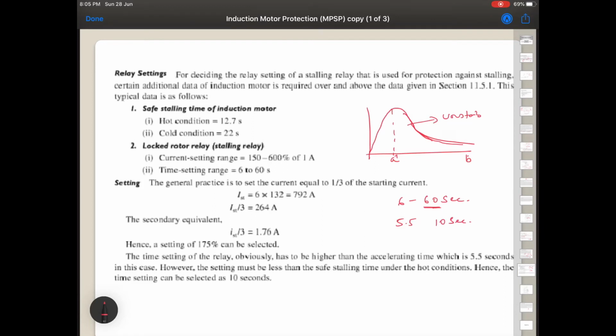And why is it overcurrent? Because the relay used is a definite time overcurrent relay. During stalling the speed is reduced, and if the speed is reduced, as already discussed, the current will be too high, so hence this relay is used. And when the speed is reduced, stalling can be sensed only based on the speed. If the speed is reduced, then there will be a speed sensor that will operate the speed relay also, and this overcurrent relay will have to operate. So these two have to operate simultaneously. If both match, that is speed is reduced as well as current is increased, it means there is stalling. And for both to operate in a cooperative manner, a centrifugal switch is used to implement this.